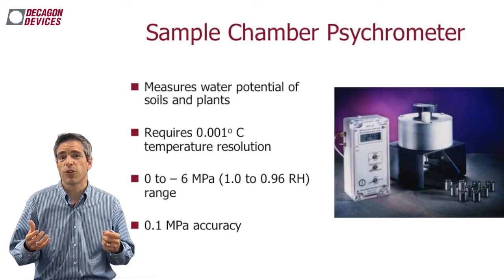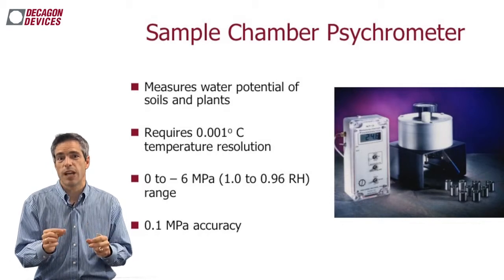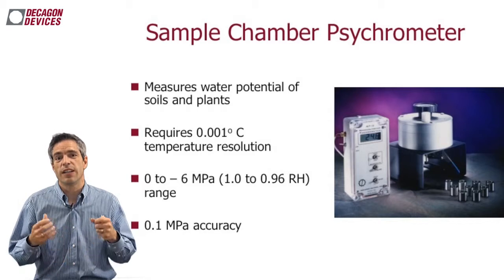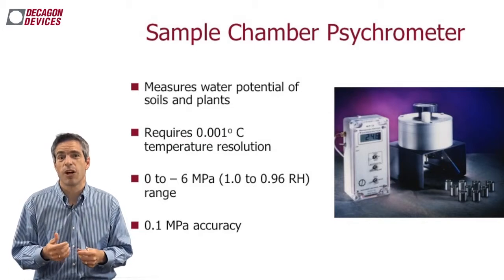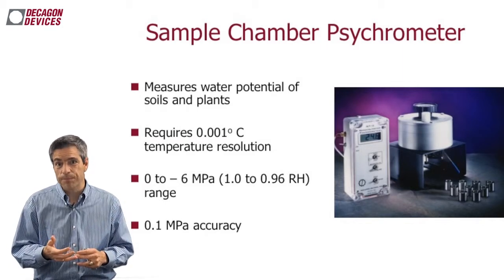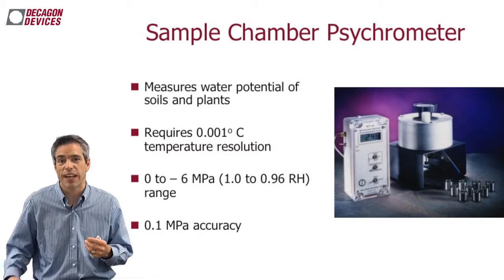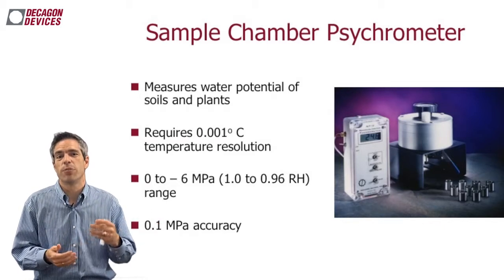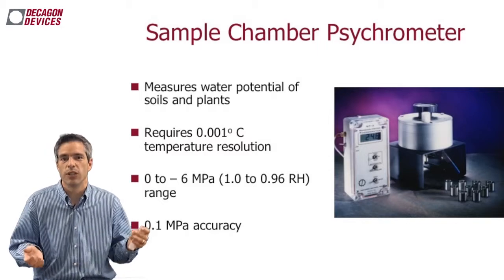There is also a lab-based thermocouple psychrometer that works differently. Soil samples are placed in sample cups inside a large aluminum block that brings everything to isothermal conditions, then a thermocouple psychrometer measures the wet bulb to get relative humidity and therefore water potential. The range is about zero to negative 6 megapascals. However, the upper limit is only about negative 0.1 megapascals, so it doesn't even resolve the plant optimal range.